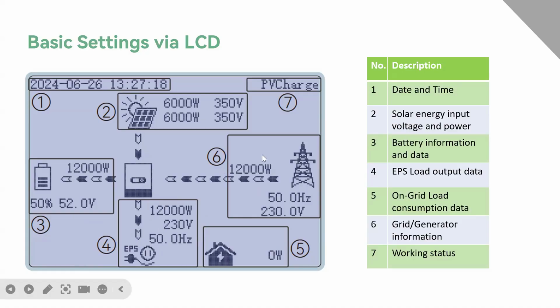And the sixth one is the grid and generator information. If you are connecting to the grid, it will show the grid, and if you are connecting to a generator, the icon will change to the generator. It also shows the frequency, voltage, and the input or output powers. And number 7 is the working status. For example, currently it is working in a certain working mode. Also, if there are errors or warnings on the inverters, you can see them here.